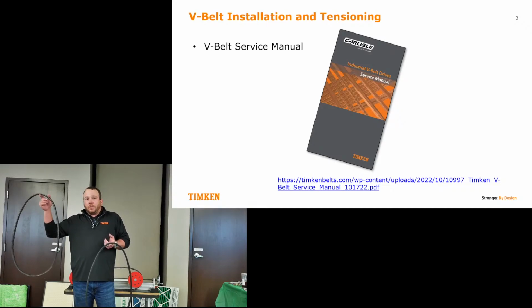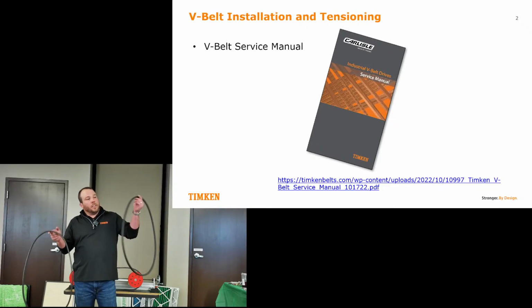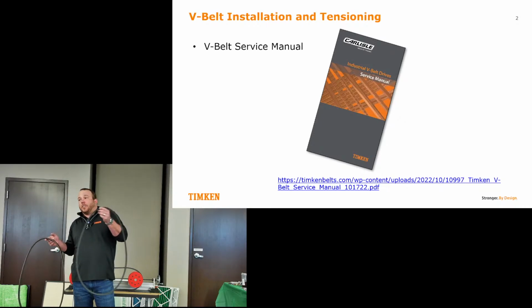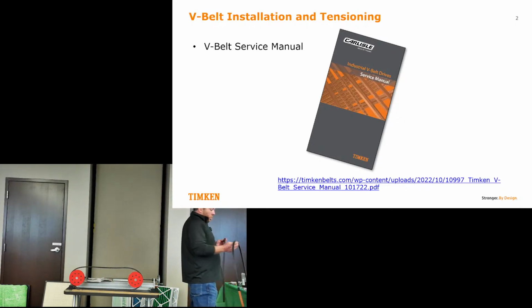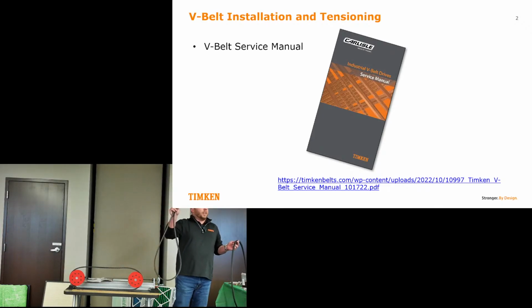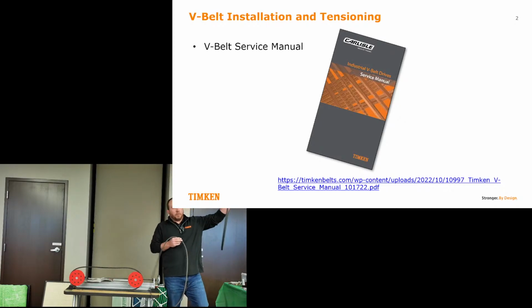This one's about 30% longer life, better performance with the rubber than this one. However, nobody's developed an EPDM material that can bond to the fabric, so therefore we have to use a different rubber product for a wrapped V-belt. So more cords, tighter radius around a sheave for more efficiency, better material. Why would you ever use a wrap V-belt?